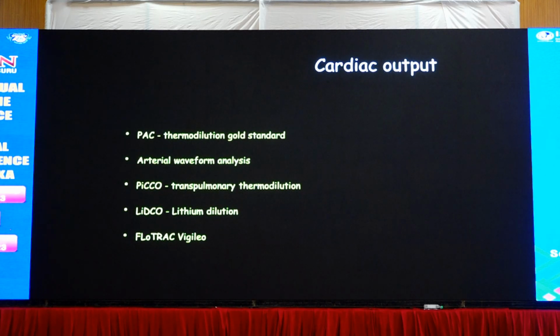The PiCCO and the LIDCO use some form of indicator dilution. PiCCO uses cold saline like in the pulmonary artery catheter, but it is less invasive as you use only the arterial line, and the LIDCO uses lithium as an indicator dilution.